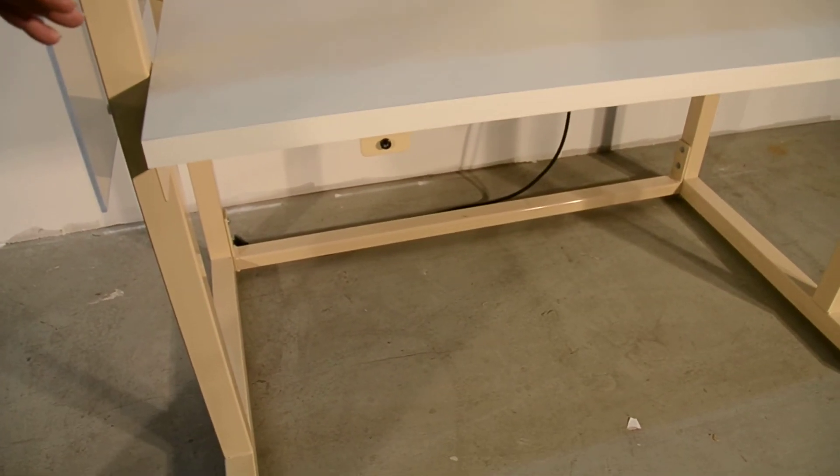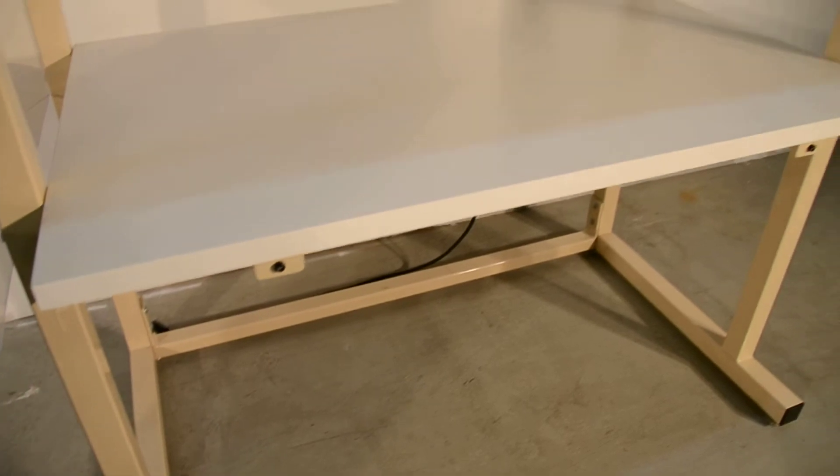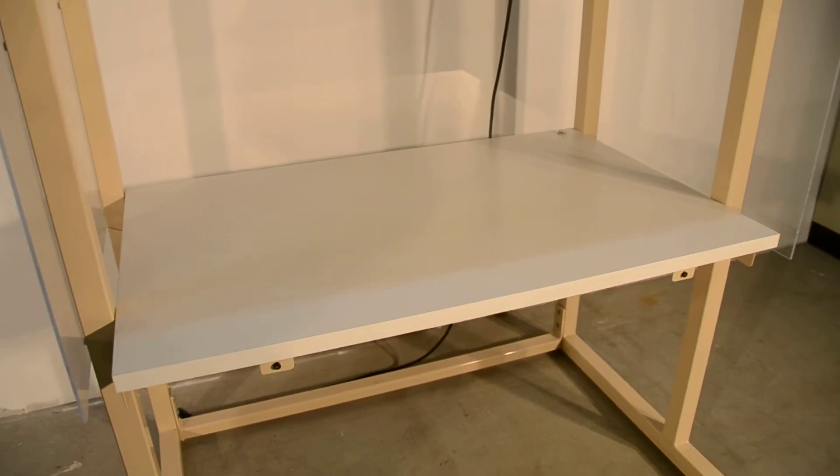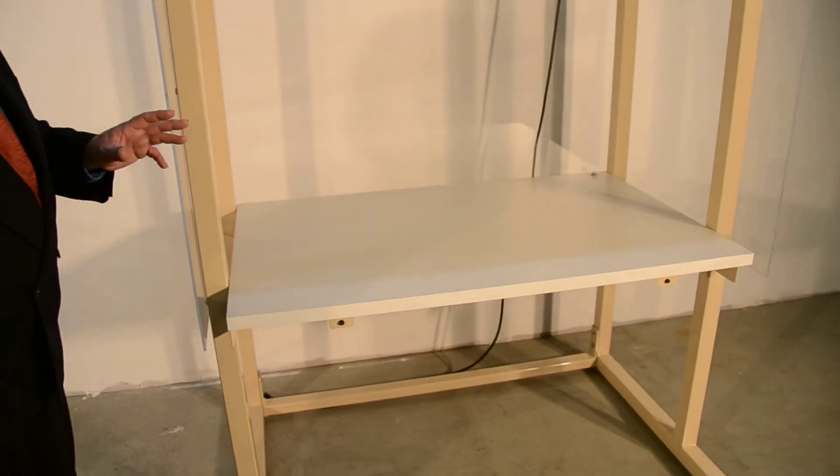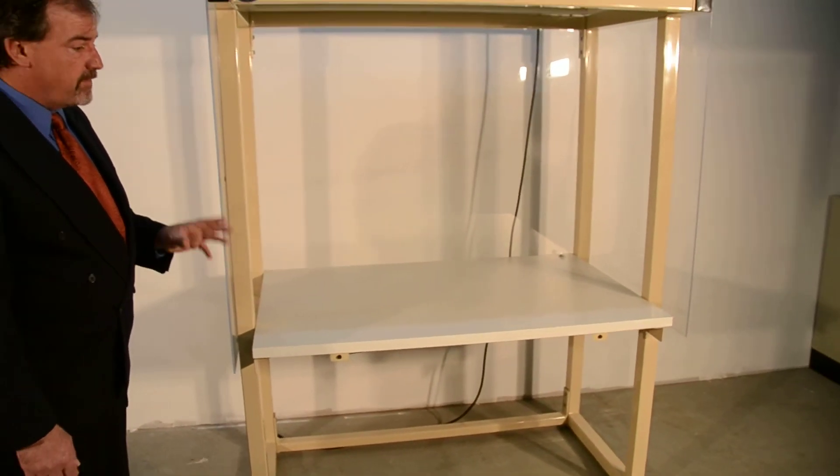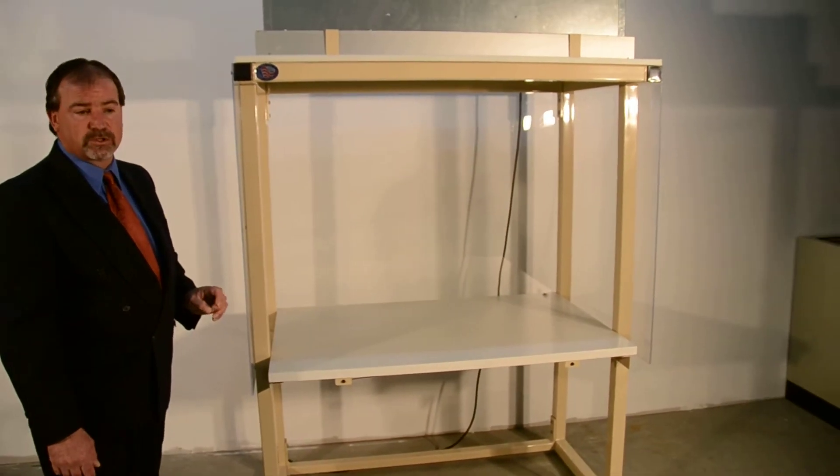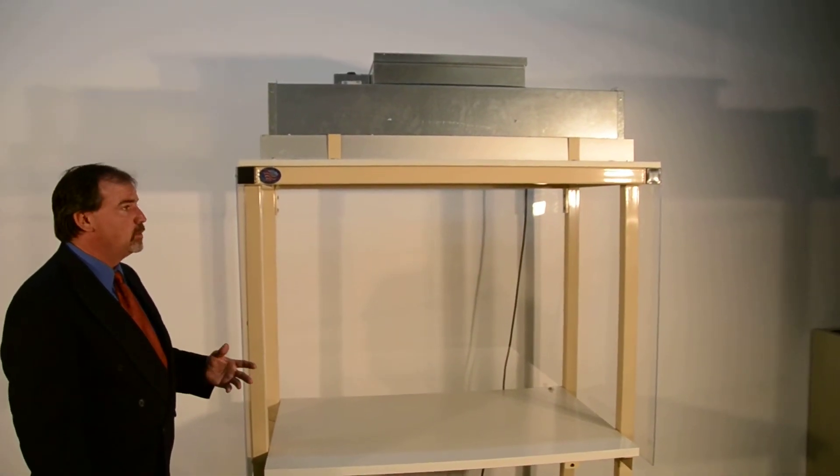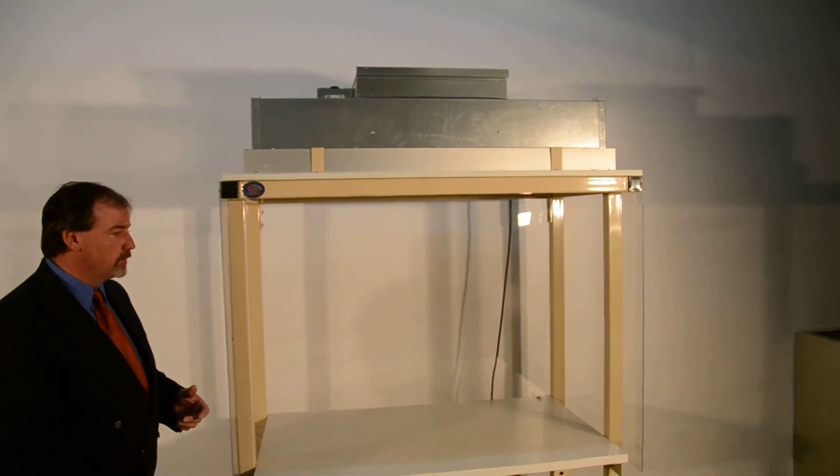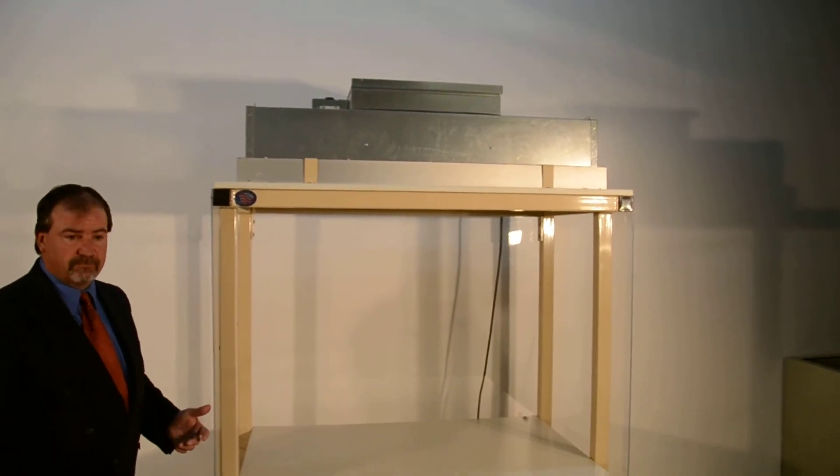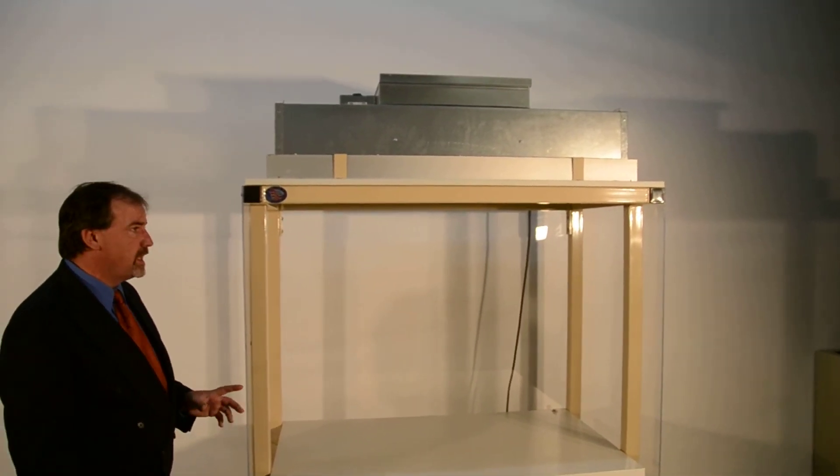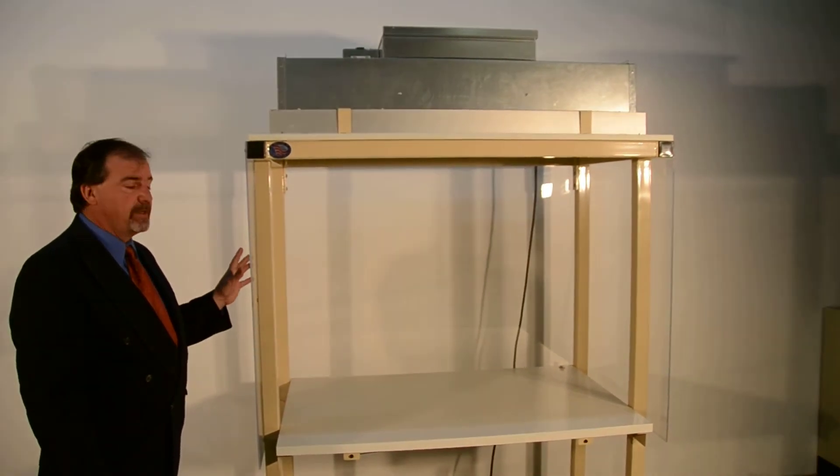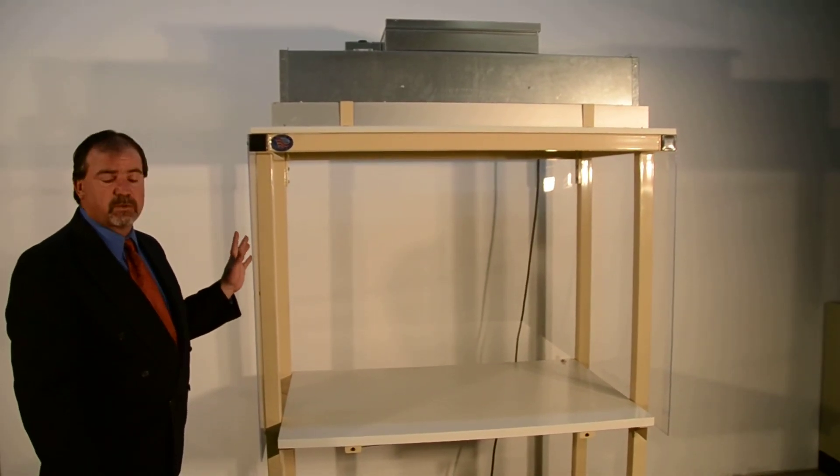This unit is available in multiple sizes from 48 up to 72 inches. This is a very inexpensive alternative to putting a full room in. Typically, when you need to build a Class 100 room, you're looking at $25,000, $40,000, $50,000, versus this unit is in the area depending on the size, around $2,700.